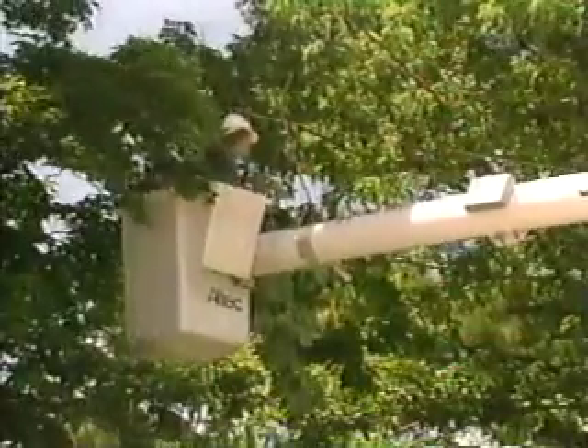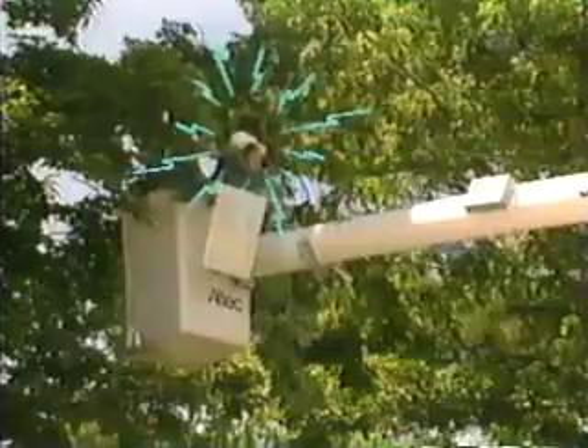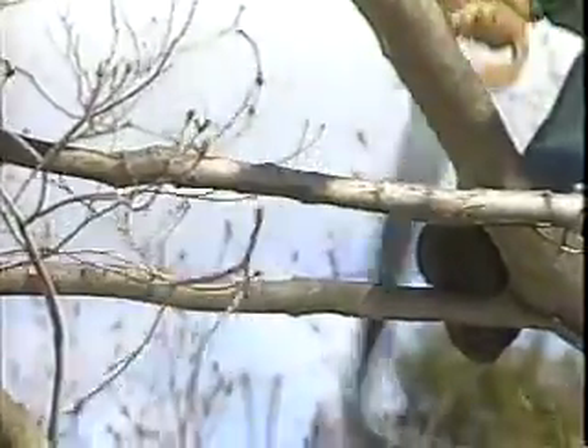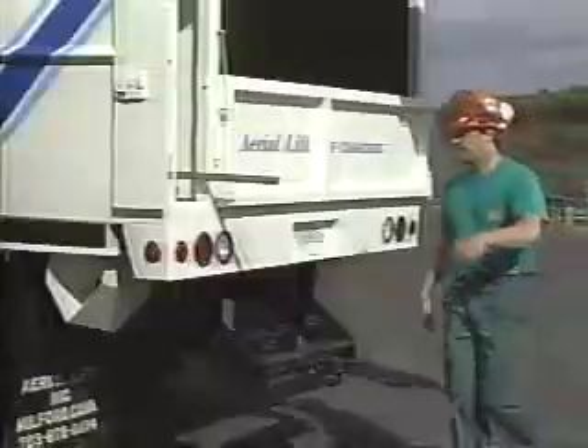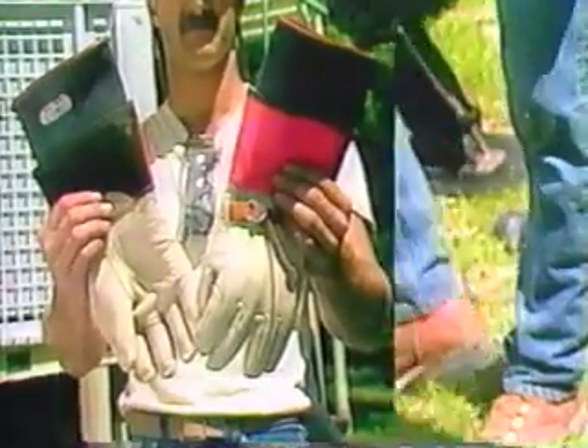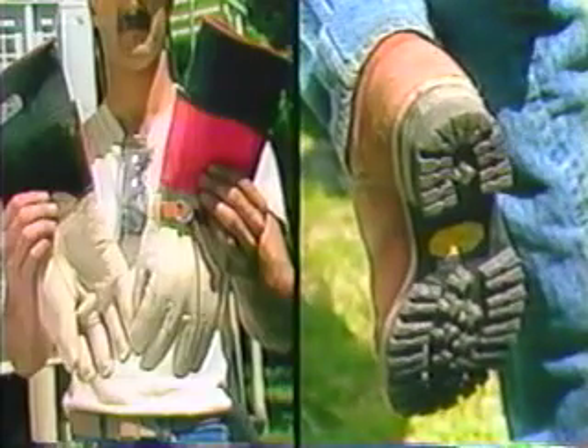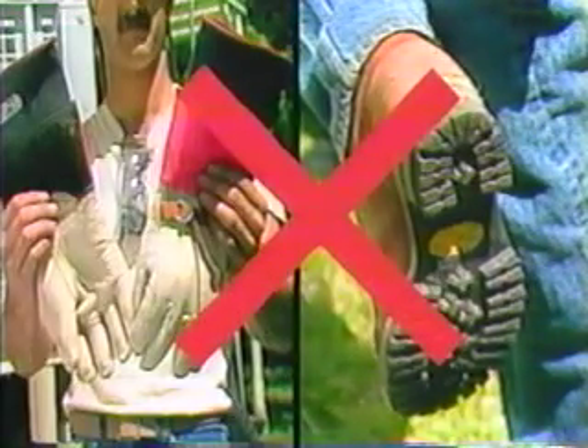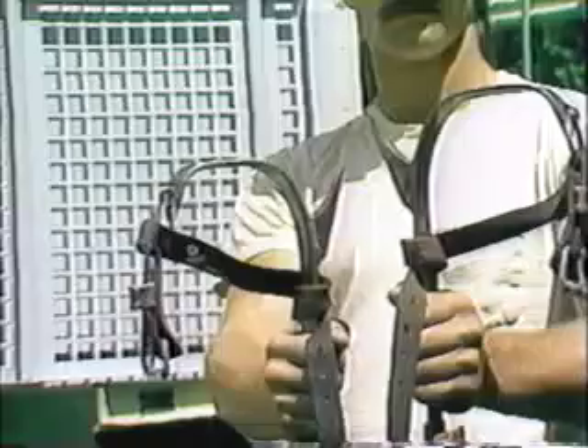Tree limbs are conductive materials, as are many of the tools which you commonly use, such as hand saws and chainsaws. Even non-conductive tools such as wooden-handled pole saws can become conductive when wet and dirty. Rubber gloves, rubber-soled shoes, or lineman's rubber overshoes are not to be considered insulated protective equipment. If a tree is in contact with an energized line, the sapwood is often more conductive of electricity than the outer bark. Therefore, if the tree in contact is to be removed, climbers should be warned.